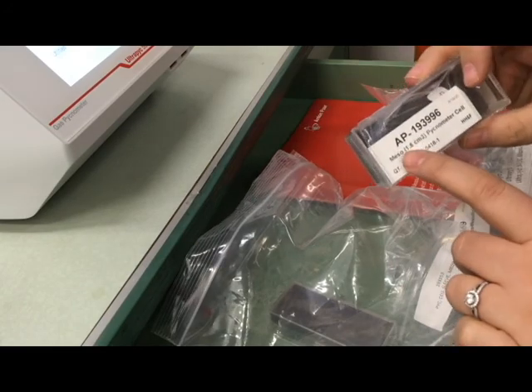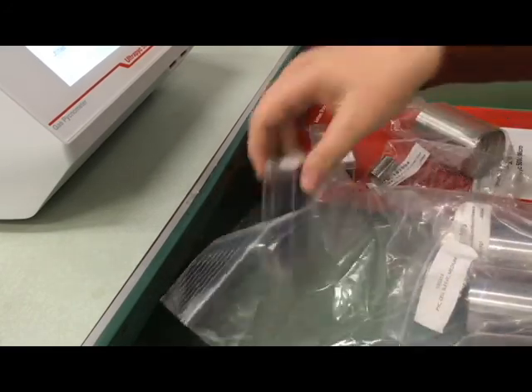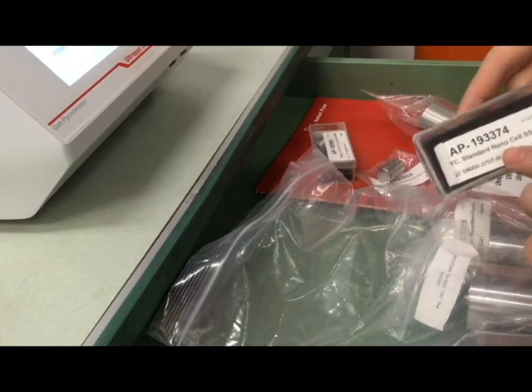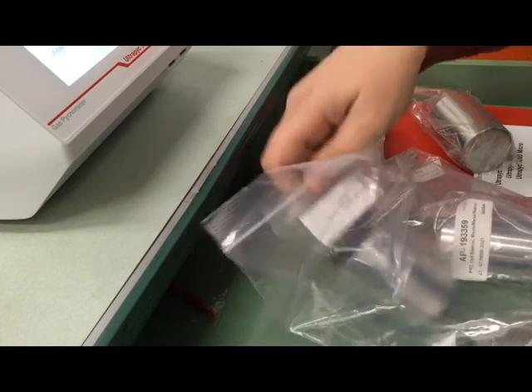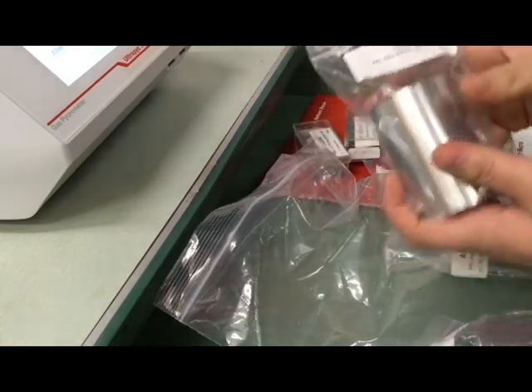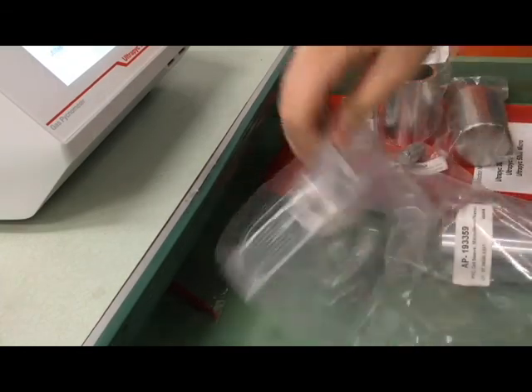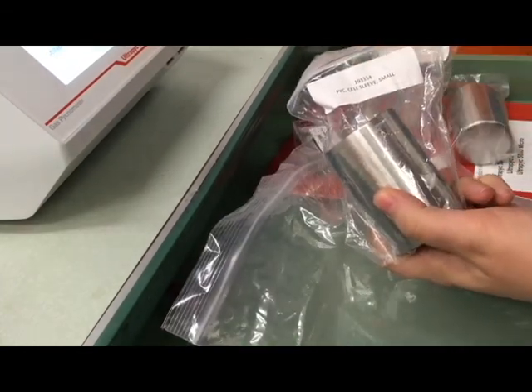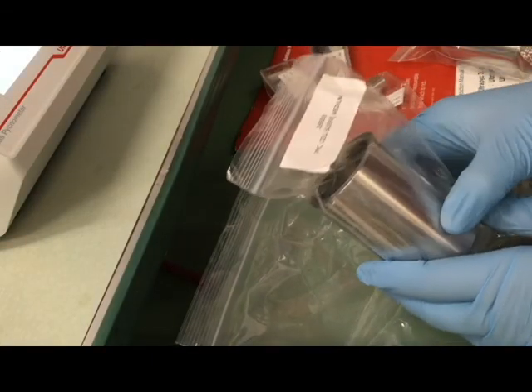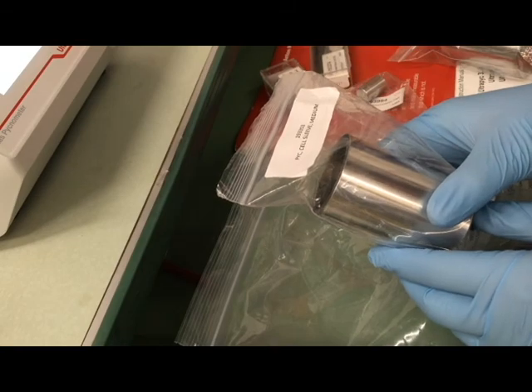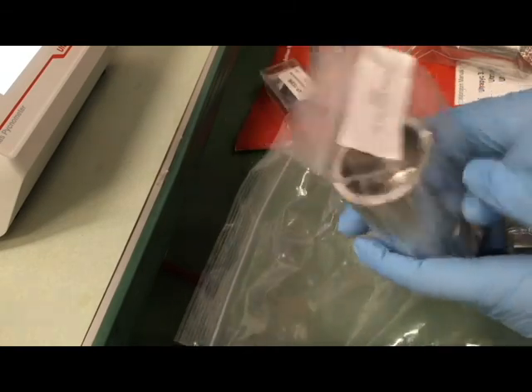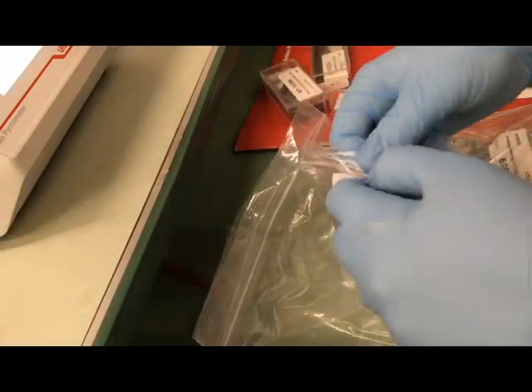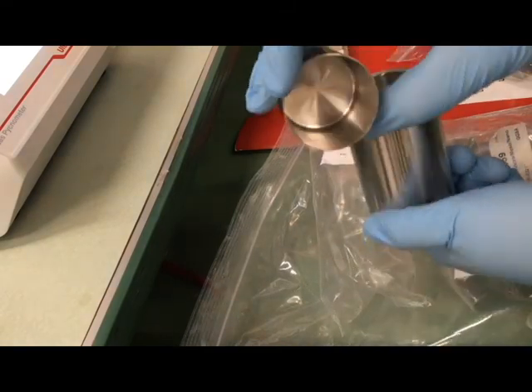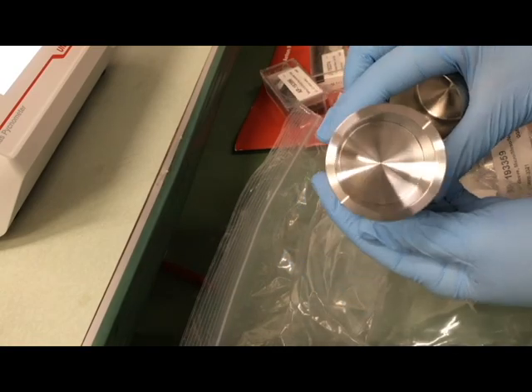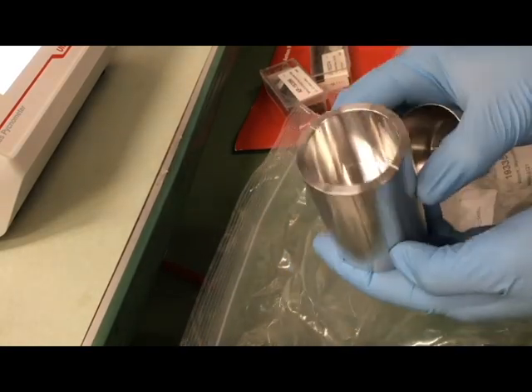Each of these cells gives us the ability to change the interior size of the instrument, and that will allow us to run different sized samples depending on how much material you have or how large your material might be. If you have anywhere between 10 and 50 centimeters cubed of material, so that's a volume there, you would use the medium cell. The medium cell has a sleeve to contain your material and a big solid base, which is going to fill up the remaining space in the sample chamber in the Ultrapyc.